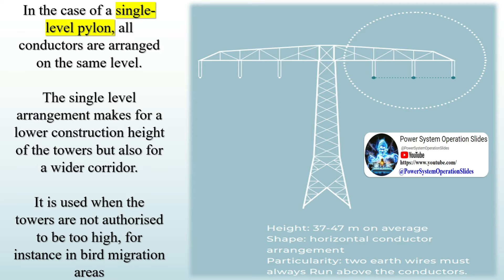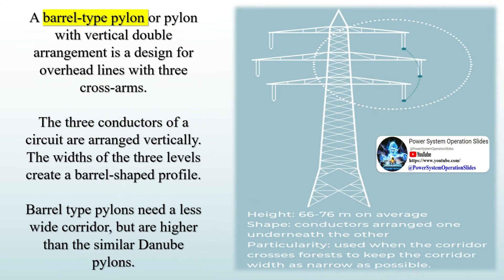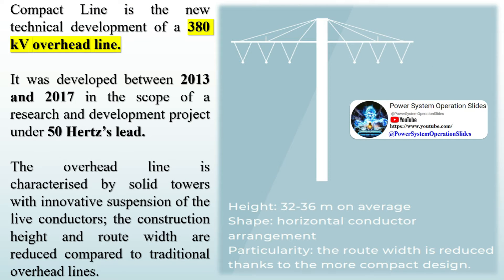The Danube or two-level pylon is a tower for two three-phase current circuits; the conductors are always arranged in a triangle, with two conductor bundles per circuit on the lower crossarm and one on the upper crossarm. In the case of a single-level pylon, all conductors are arranged on the same level. The single-level arrangement results in a lower construction height but a wider corridor, and is used when towers are not authorized to be too high, for instance in bird migration areas. A barrel-type pylon, or pylon with vertical double arrangement, is a design with three crossarms where the conductors are arranged vertically. Barrel-type pylons need a less wide corridor but are higher than similar Danube pylons. The compact line is a new technical development of a 380 kV overhead line developed between 2013 and 2017, characterized by solid towers with innovative suspension of live conductors, with reduced construction height and route width.